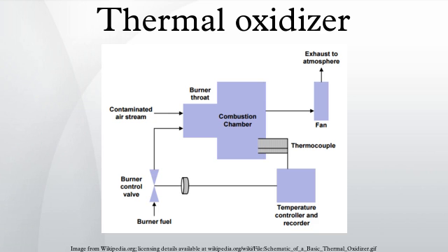On start-up, the system preheats by raising the temperature of the heat exchanging ceramic material in the bed at or above the auto-oxidation temperature of methane 1000 degrees Celsius, at which time the preheating system is turned off and mine exhaust air is introduced. Then the methane filled air reaches the preheated bed, releasing the heat from combustion. This heat is then transferred back to the bed, thereby maintaining the temperature at or above what is necessary to support auto-thermal operation.